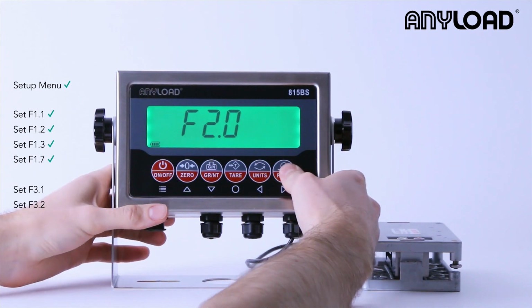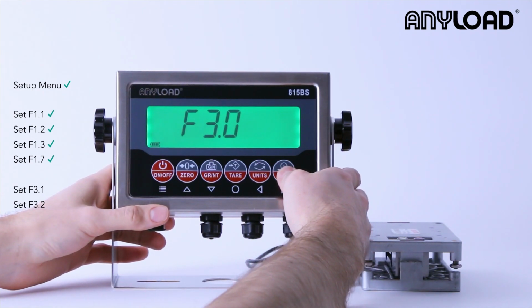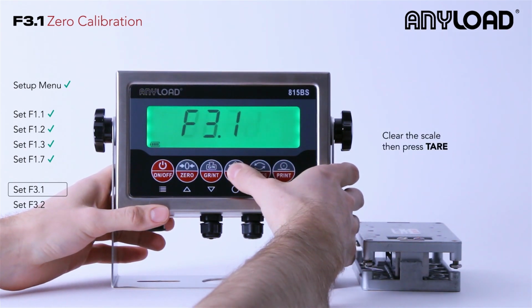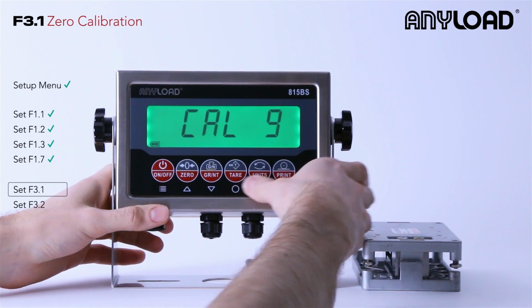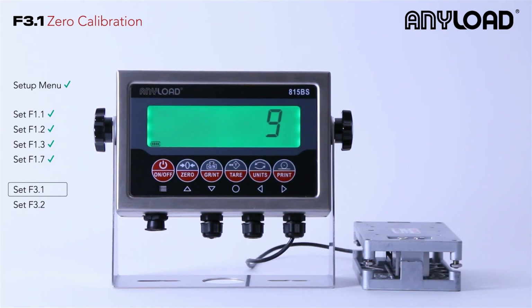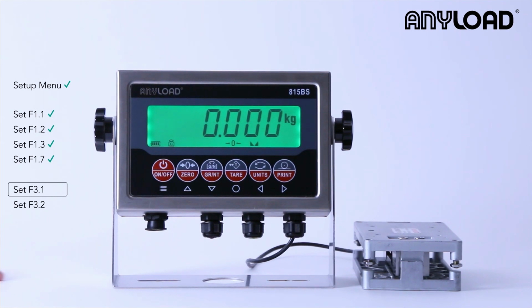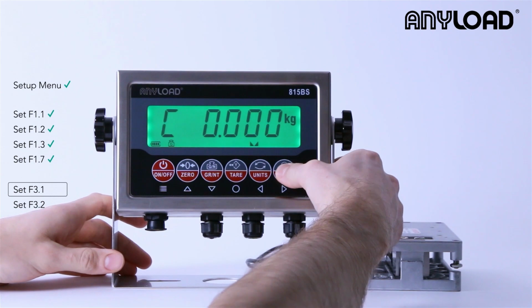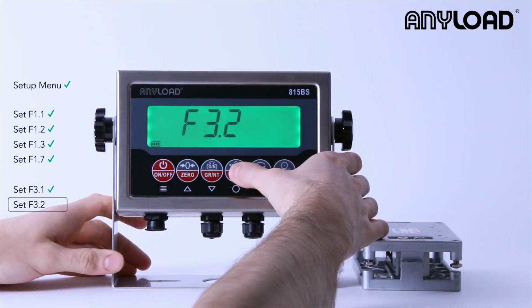Now we're going to navigate to our F3 settings. F3.1 is our zero calibration. It's going to ask us to clear the scale. Once you've cleared the scale, press tare, and it's going to begin that calibration countdown from 10. Don't touch the scale while this is happening, just let it do its thing. So we're going to go directly to our F3.2 setting, which is our span calibration.